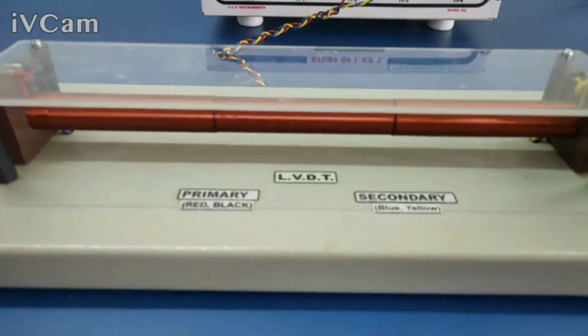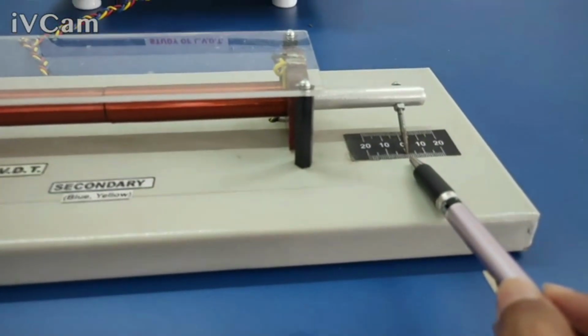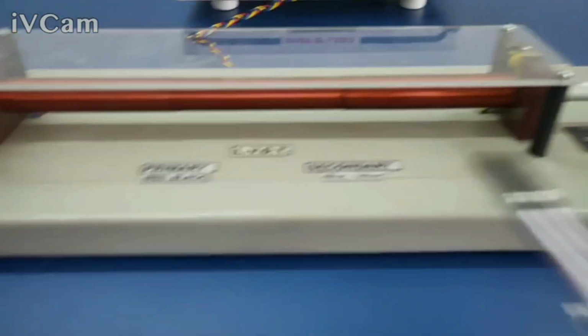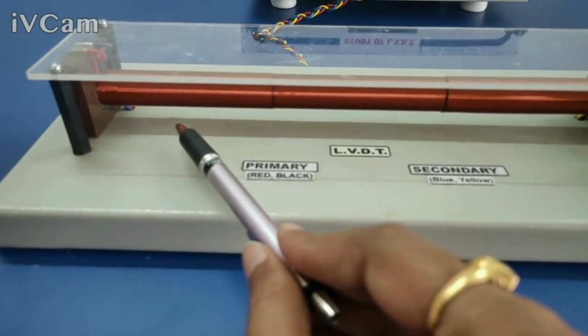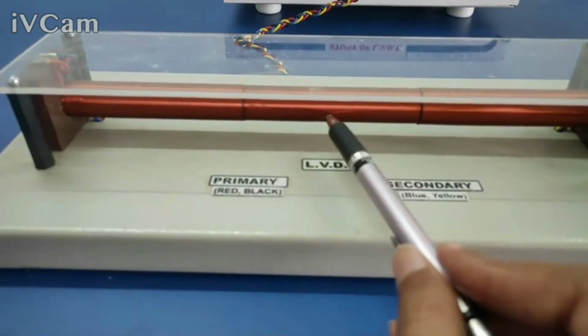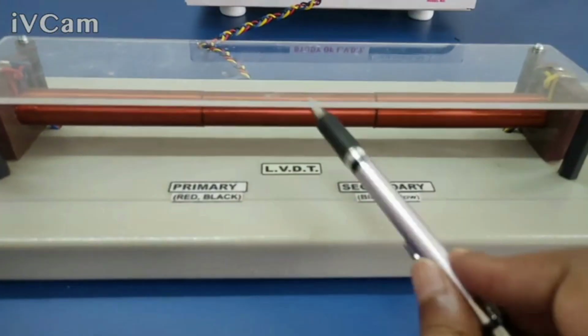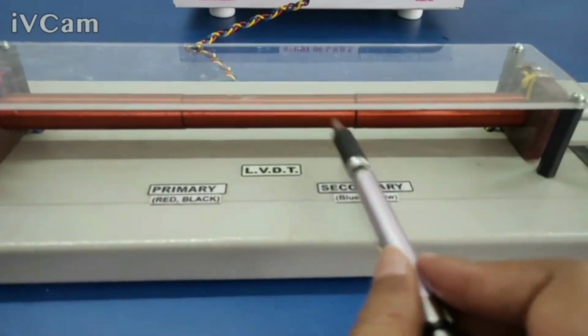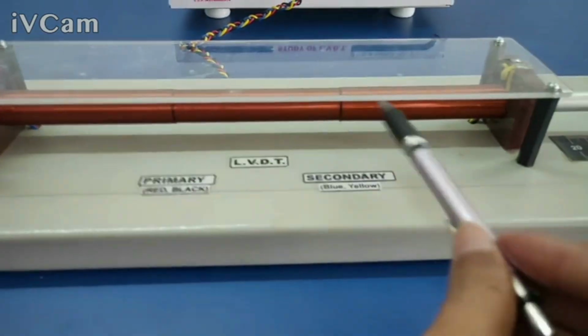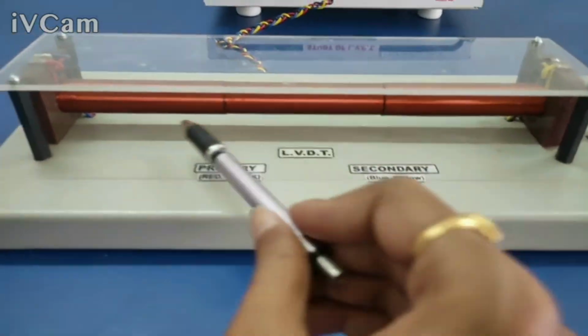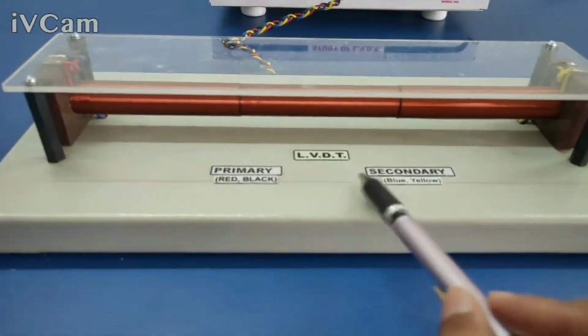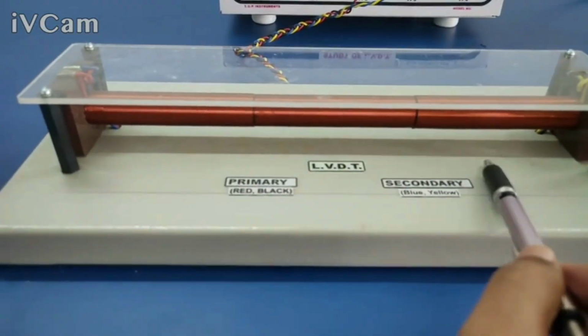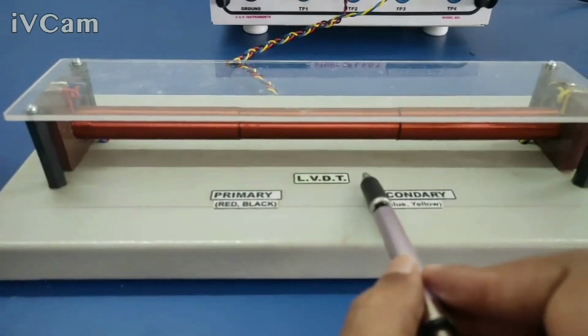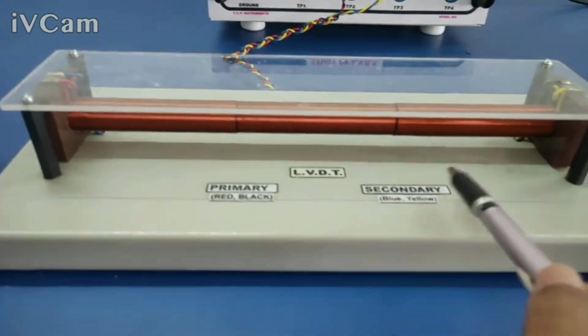Now when the core is at the exact center position, what we call the zero position or null position, the part of the core towards the left-hand side, that is secondary winding number 1, and the part of the core towards the right-hand side, that is secondary winding number 2, are the same. Hence the flux linkages at the two secondary windings are the same, that is ES1 and ES2 are both the same. So when ES1 and ES2 are both the same, the net output, ES1 minus ES2, will be absolutely 0.